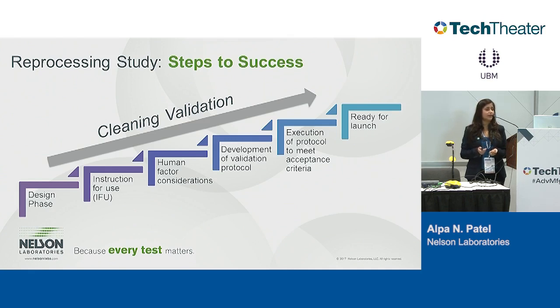These are some of the steps that I have outlined that if you think of cleaning validation, or if you're thinking of a reusable medical device at your facility, or you are manufacturing any of those, these are the steps that you want to consider. Design phase should be the first. When you think about cleaning validations, that should be the first thing that you want to consider, because when you don't consider it, the device cannot be sterilized or cleaned. Many times there are disinfectants that can discolor your device, or lubricants may not adhere to it and break them apart. So it's very important to ensure that these materials can handle the reprocessing supplies for it.